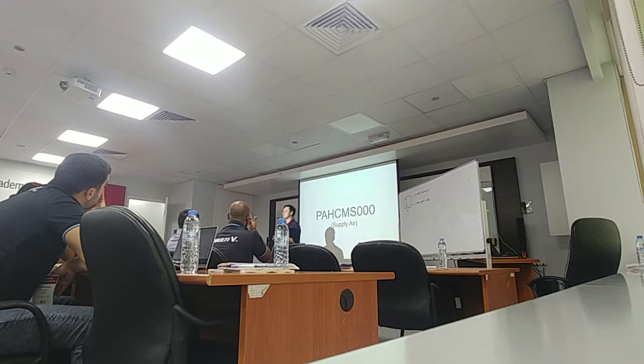Also we found that the communication speed of this product is 9600 bps, post generation. Also it took about 8 or 10 minutes to auto address. So also somehow one or two teams failed to auto address, but after resetting, finally found the address the second time. So it took like 20 minutes to get the addressing.